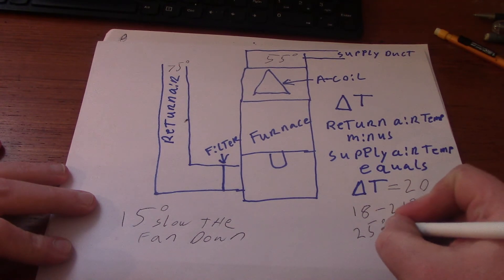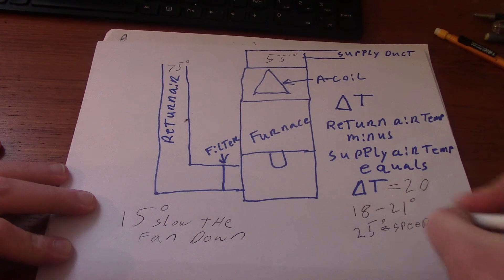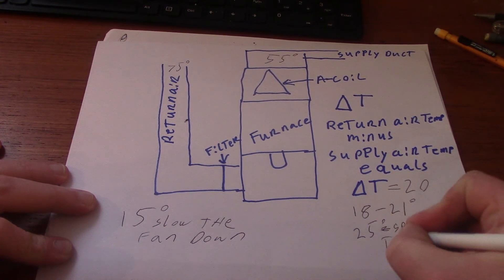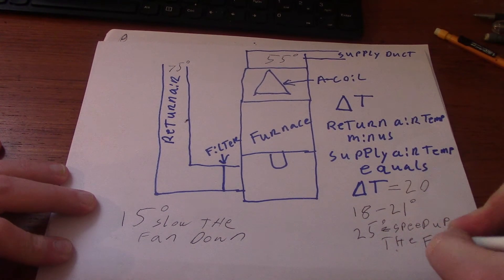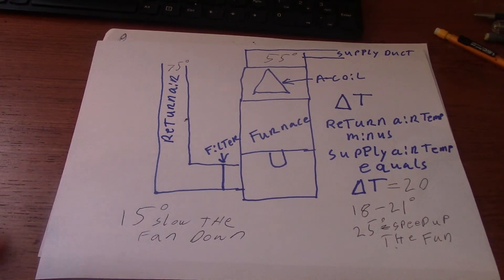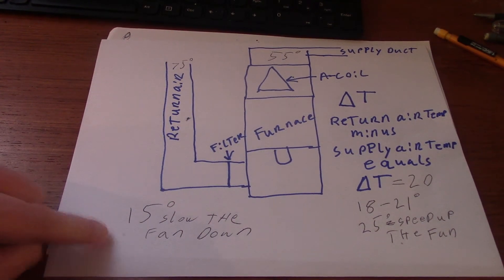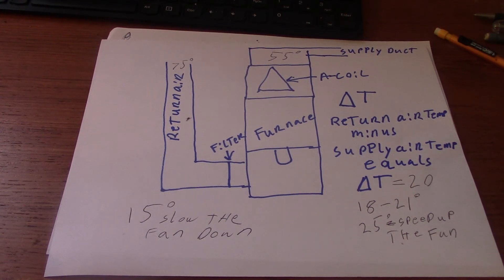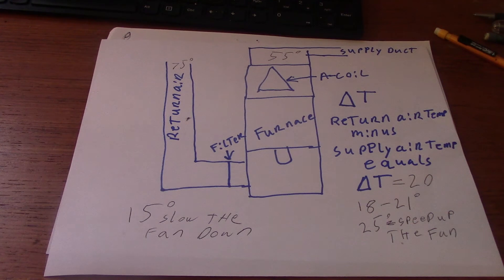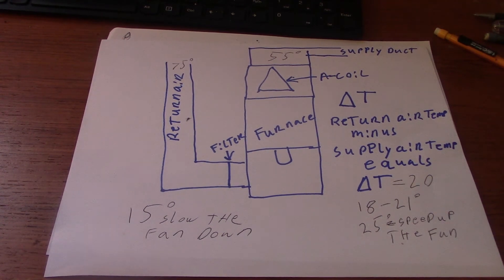So if you're at 25 degrees, you need to speed up the fan. If it's on medium speed, kick it up to high speed. For the 15, if it's on high speed, put it down to medium or medium high speed, to get it proper for it to work efficiently and appropriately.